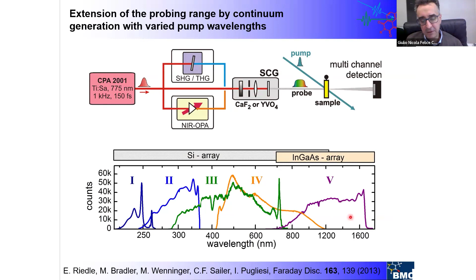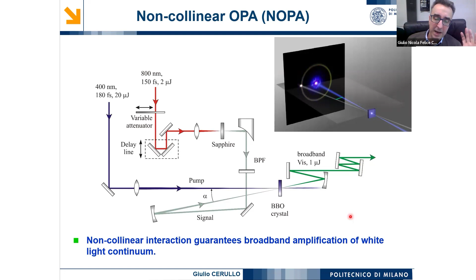Now, another thing that I want to mention is that using this optical parametric amplifier, you can also make very short pulses. If you use the so-called non-collinear OPA, the non-collinear interaction guarantees a broadband amplification of a white light continuum, and you can generate really short pulses. In fact, here I'm showing you some of the pulses that we generate in our labs using these non-collinear OPAs, which have a duration of less than 10 femtoseconds. This is, for example, a pulse in the visible with a duration of 5 femtoseconds.